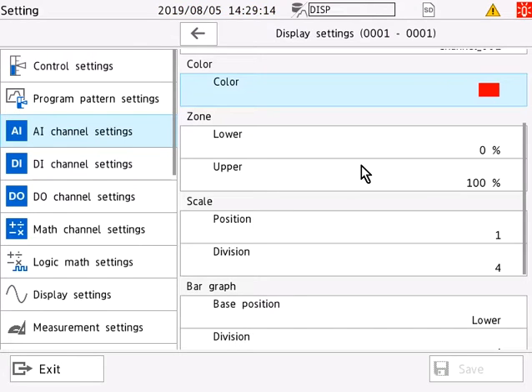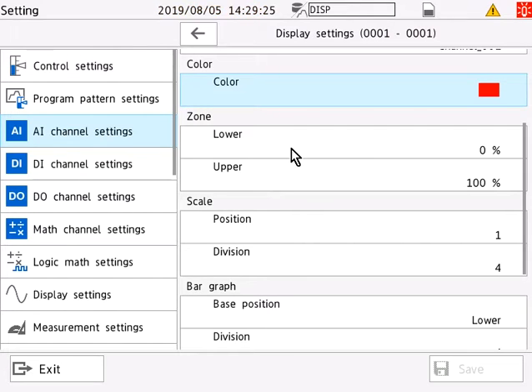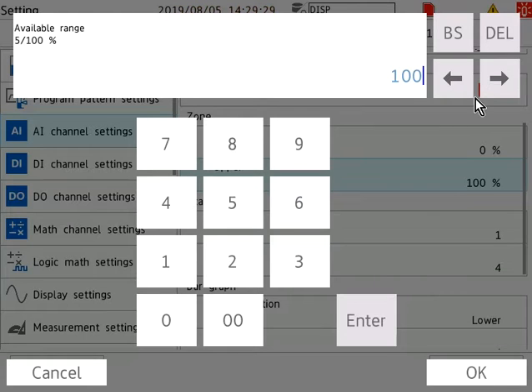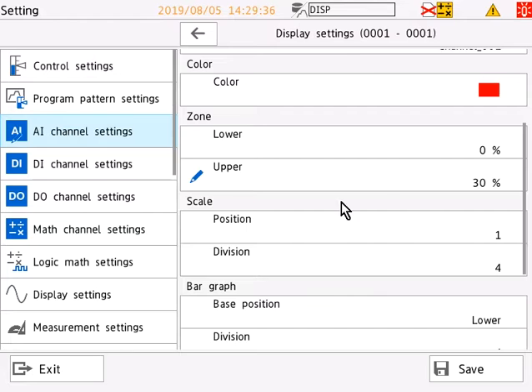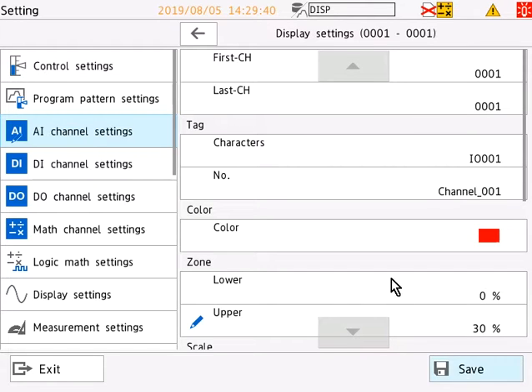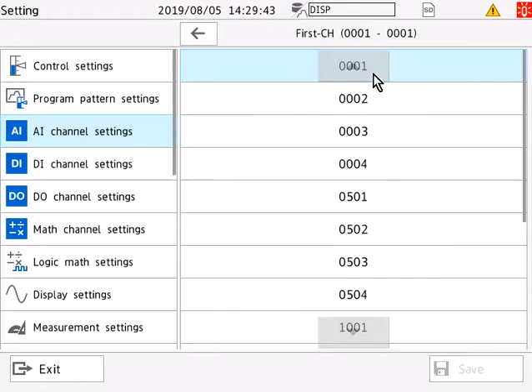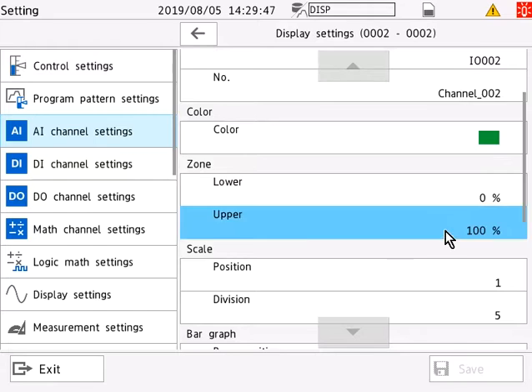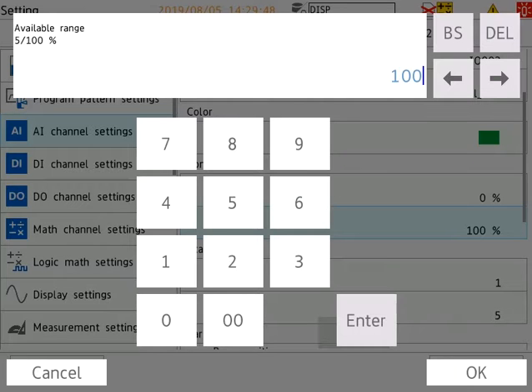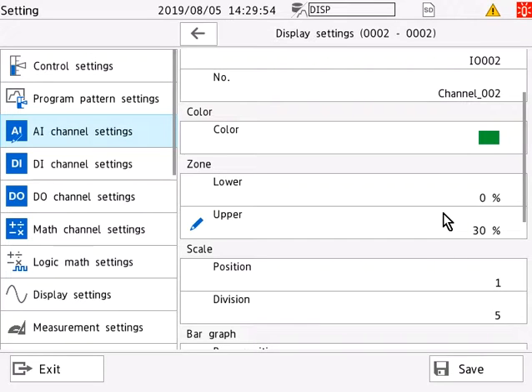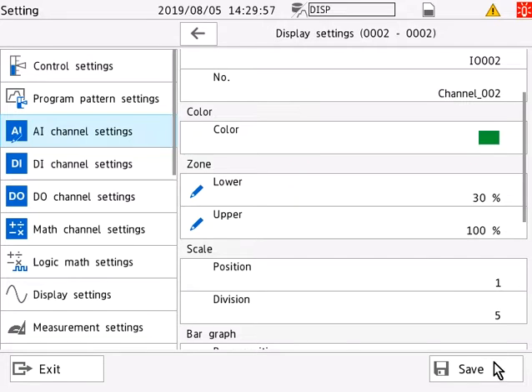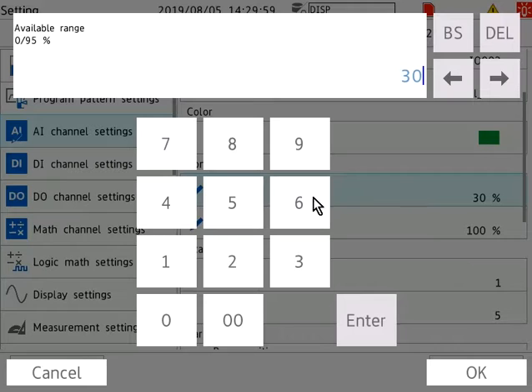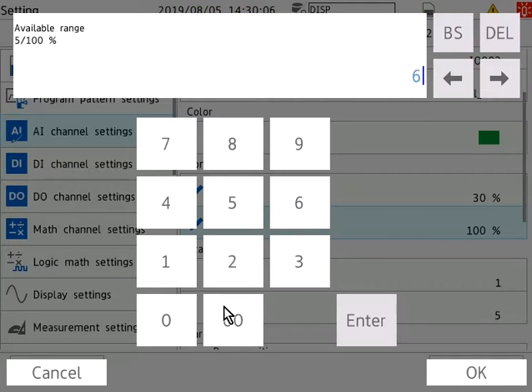For example, if we have three different thermocouple inputs all measuring three different temperatures of three different objects and we would like to see each of their trends divided vertically within the same graph, we would select the first thermocouple input to take up a zone of 0 to 30%. Scroll up, confirm that this is the first thermocouple, save. Then, we select the second thermocouple, which is the color green on the trend. Set this from 30 to 60% because the first input took up the display from 0 to 30%.